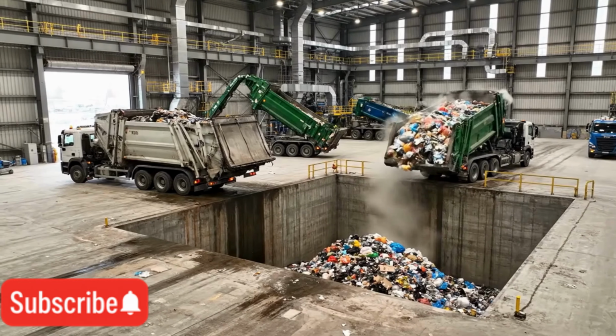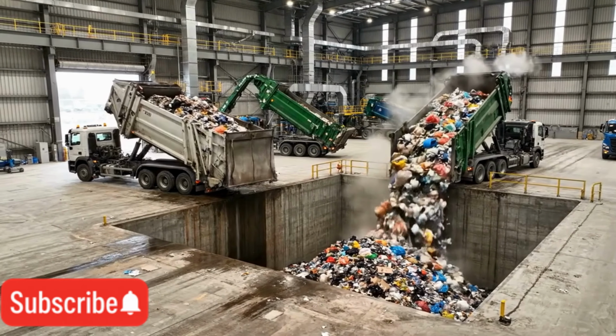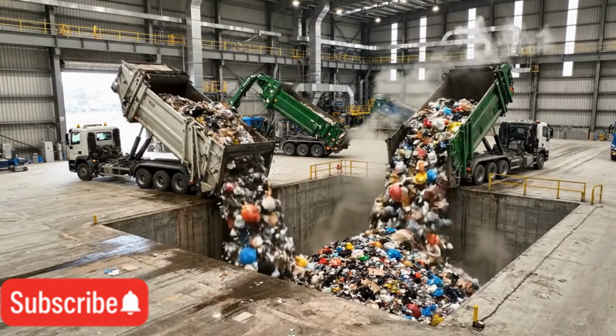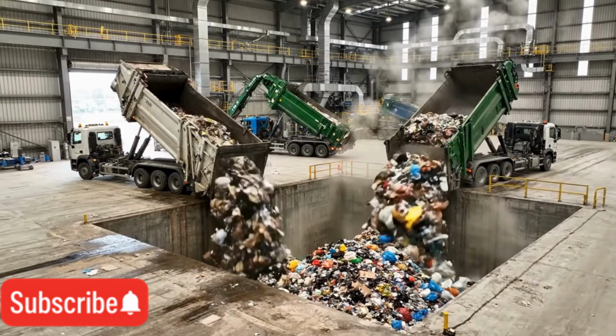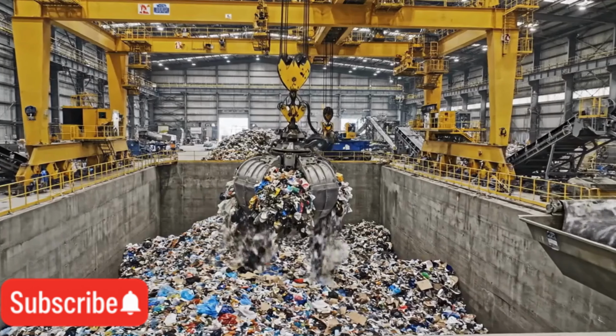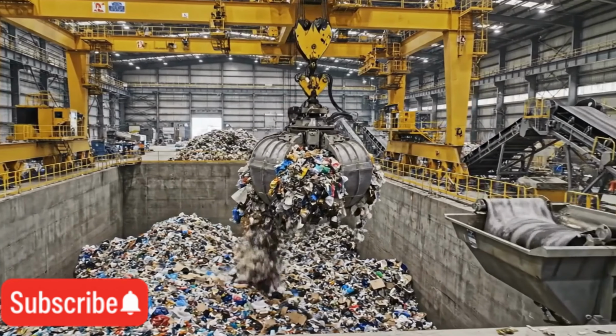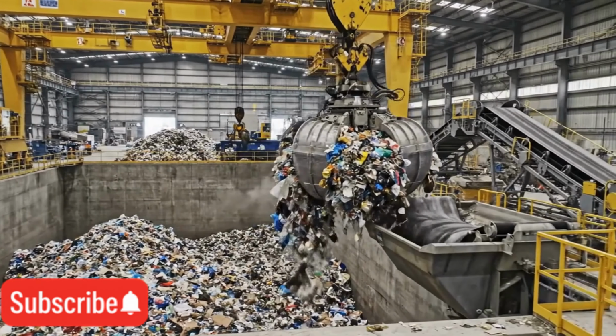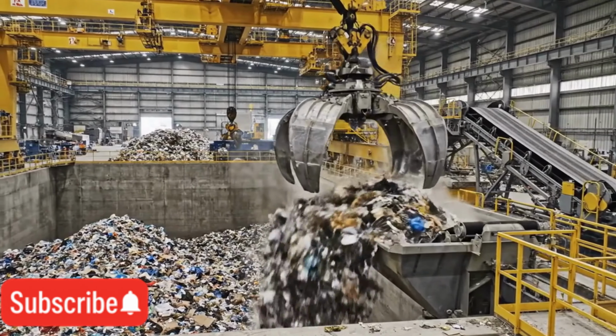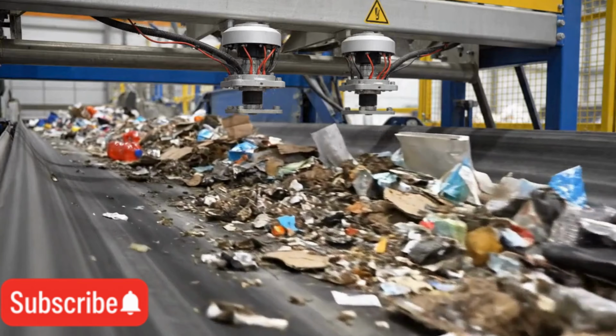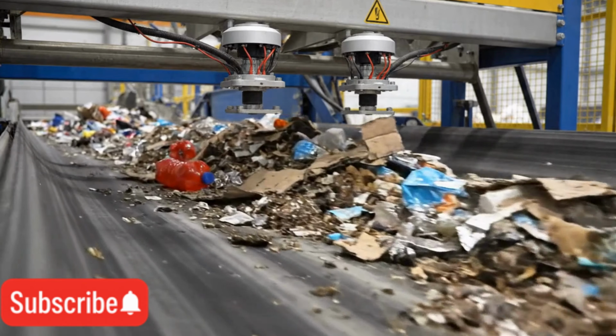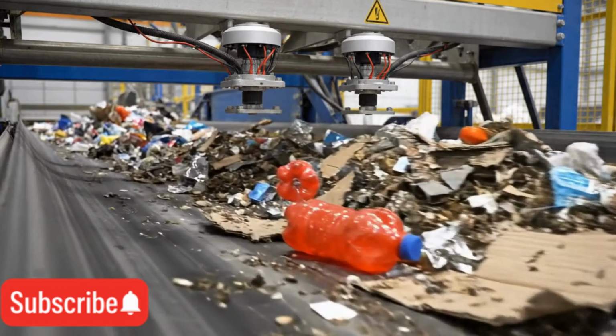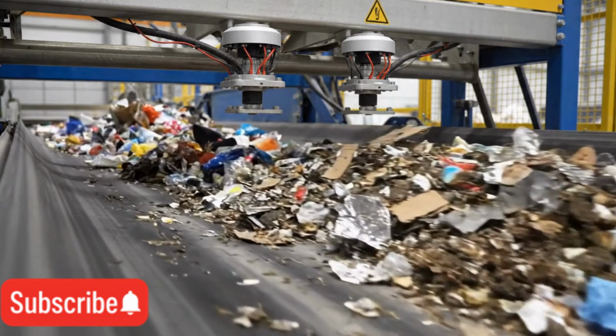processed. Inside the enclosed tipping hall, trucks discharge mixed household waste into a deep reception pit, designed to control dust and odors. A fully automated overhead crane continuously transfers waste from the pit to the feed conveyors, optimizing the load for stable gasifier operation. The main feed conveyor is equipped with variable speed drives and level sensors, keeping the flow of waste constant and precisely controlled.